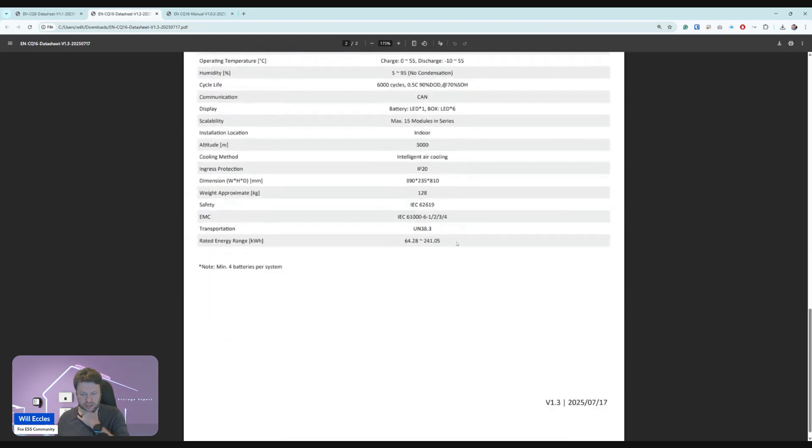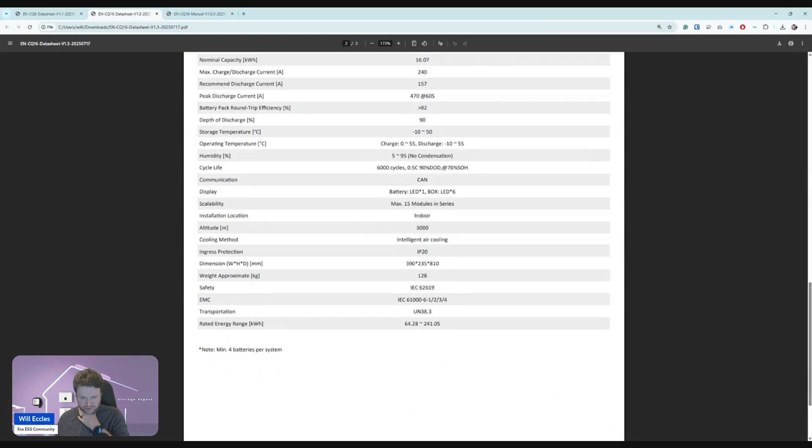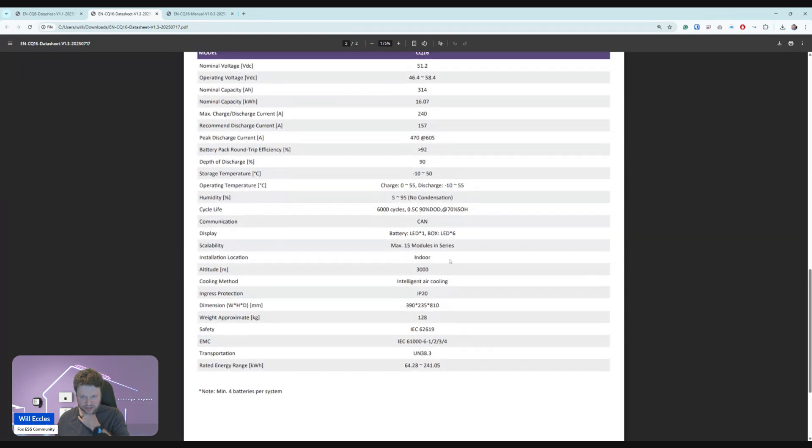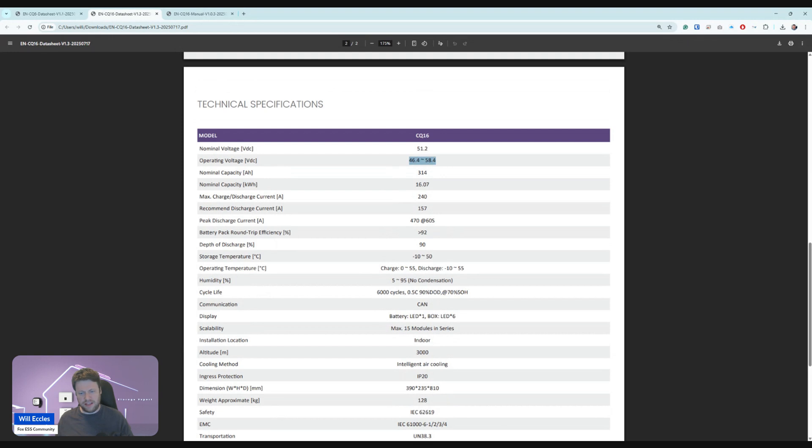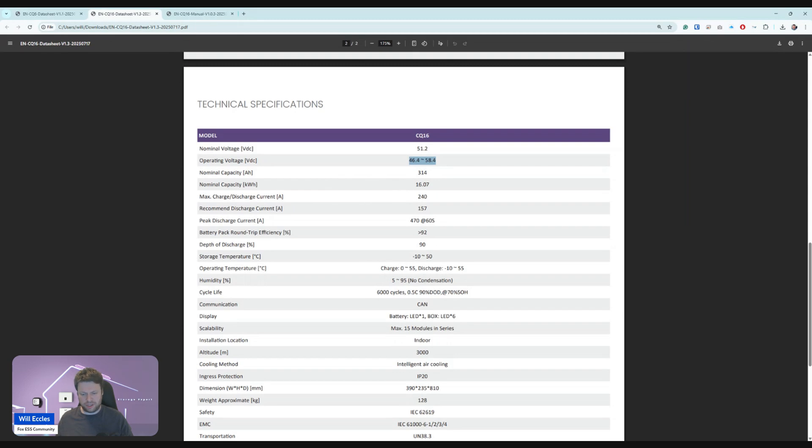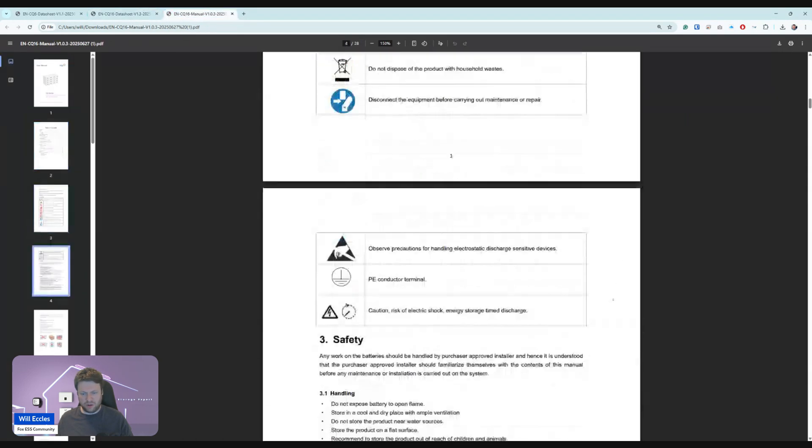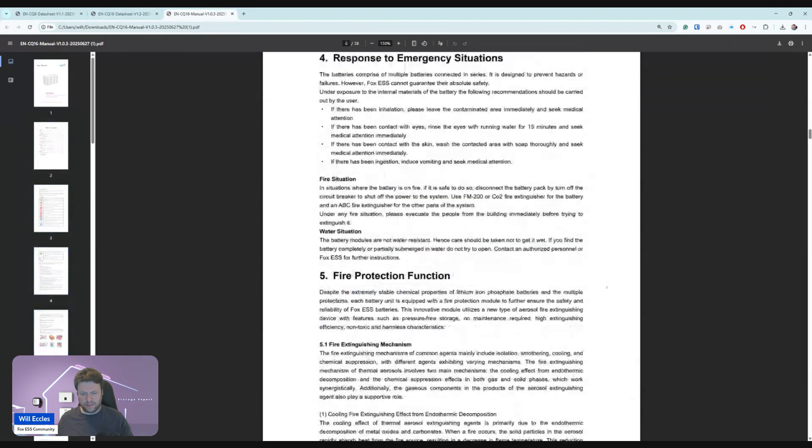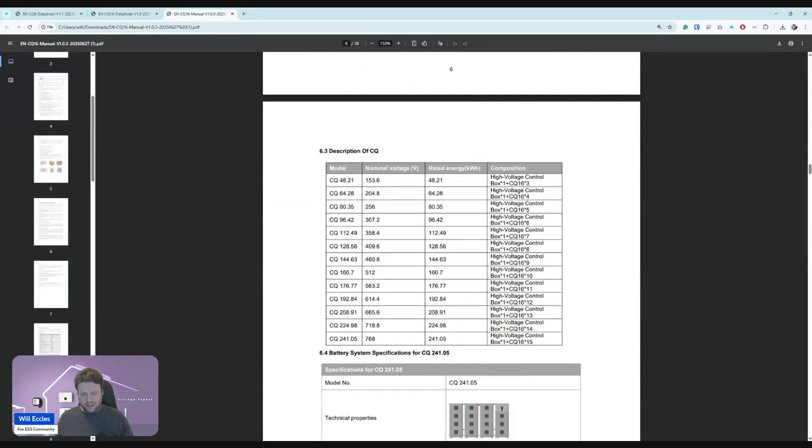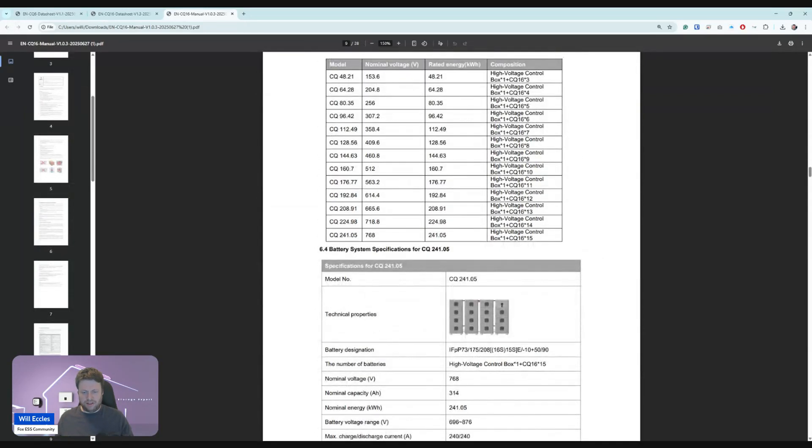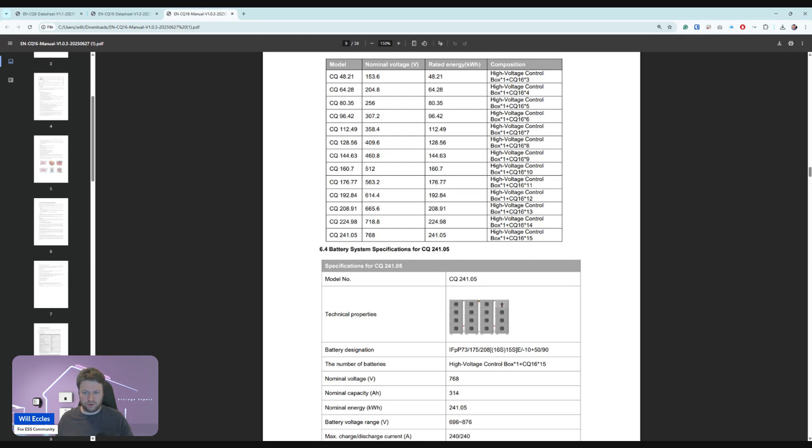This one, again, the voltages go right up to, where is it? So the voltages earlier might have been in the manuals, over 700 volts. Each module itself is that sort of normal LFP style cell, 46 to 58 volts. Normal capacity is very high charge and discharge amperage available. If we have a look in the manual, we can see the operating voltages. So if you've got a full stack of these, combining them all, you're going to be at 768 volts, giving you that 241 kilowatt hours worth of storage.